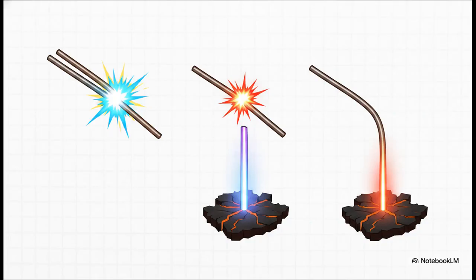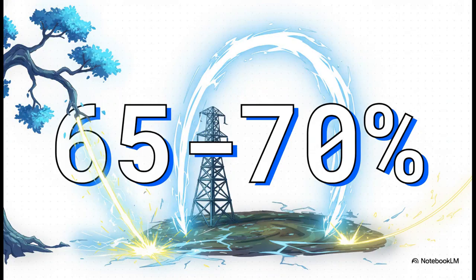So breaking down those common unsymmetrical faults, it's really all about what wires are touching each other or touching the Earth itself. We've got line-to-line faults, where two phase conductors short together. Double line to ground, where two lines short and also touch the Earth. And lastly, the single line to ground, or LG fault, where just one single wire makes an abnormal connection with the dirt. Which brings us to a pretty staggering number, 65 to 70%. Astonishingly, almost 70% of all faults on the entire global power grid are just one single line touching the ground, that LG fault.